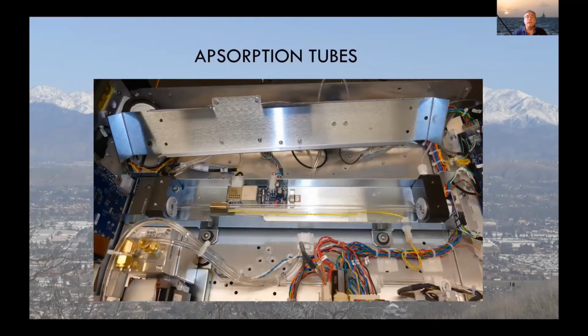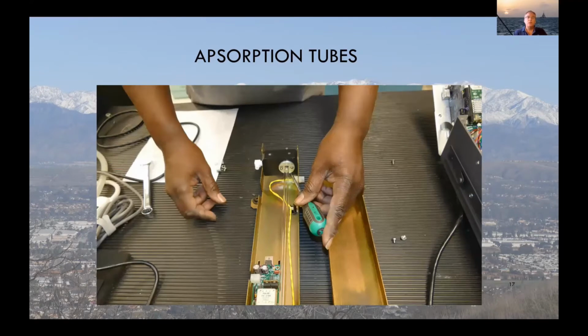Now we removed the top of the sample bench so that we exposed the absorption tube in this unit. Some units, I think the 49i, have 2 absorption tubes, double pass, but the Teledyne T400 only has the single absorption tube. They both work on the same theory though. Absorption tube maintenance is one of the critical maintenance items, and that's why we're going to cover it first.